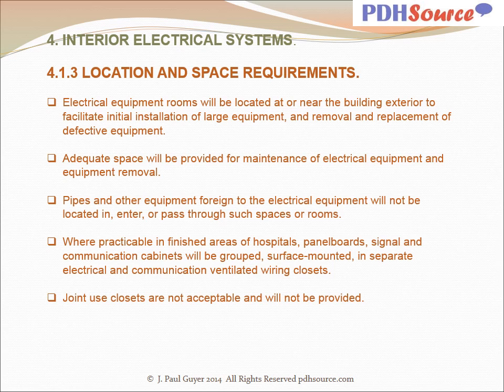Electrical equipment rooms will be located at or near the building exterior to facilitate initial installation of large equipment and removal and replacement of defective equipment. Adequate space will be provided for maintenance of electrical equipment and electrical equipment removal. Pipes and other equipment foreign to the electrical equipment will not be located in, enter, or pass through such spaces or rooms. Where practicable, in finished areas of hospitals, panel boards, signal, and communication cabinets will be grouped, surface mounted in separate electrical and communication ventilated wiring closets. Joint use closets are not acceptable and will not be provided.